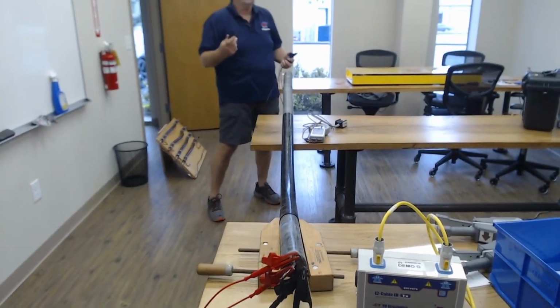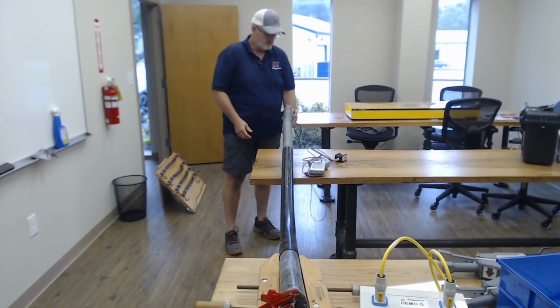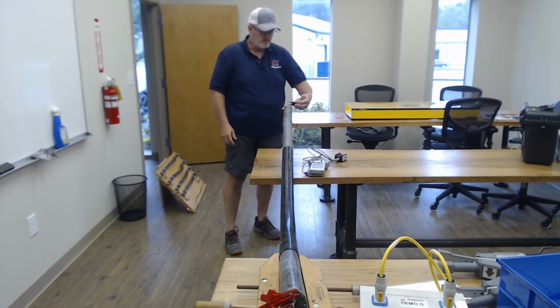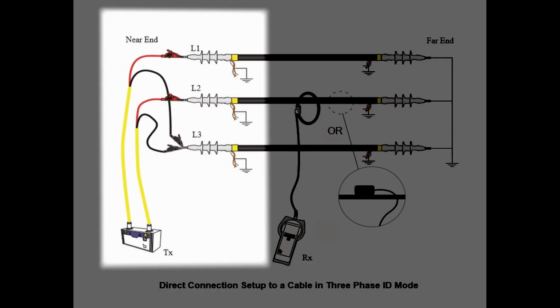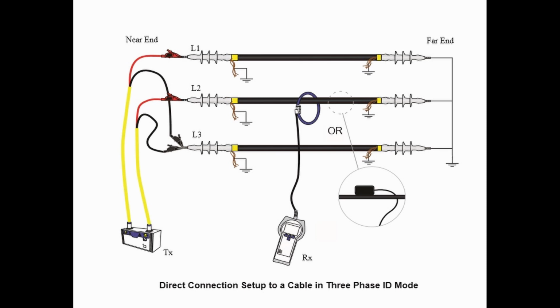You just go connect a jumper on the far end of the cable. So again, same deal as before. The jumper goes from A phase to B phase to C phase. You can, if you want. Right now, all I've done is jumpered them, which is all you need technically for this to work.